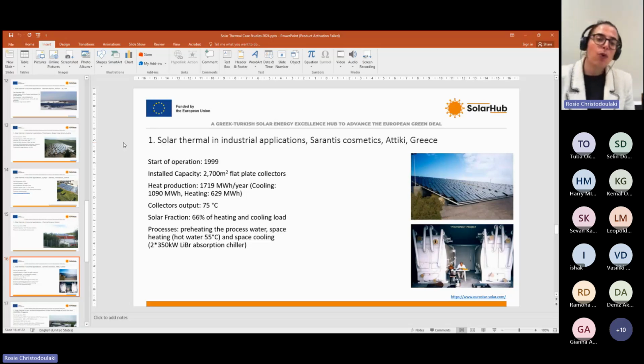This is divided into cooling production and heating production, because this system does not supply only heating, but also, as you can see in the figure below, it consists of two large lithium bromide absorption chillers. So it converts this solar thermal heat into cooling energy. This amount of heat that is produced is divided into cooling production of approximately 1,100 megawatt hours, and heating production of approximately 600 megawatt hours per year.